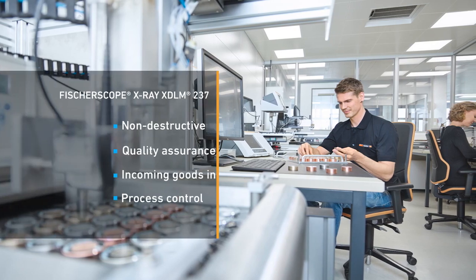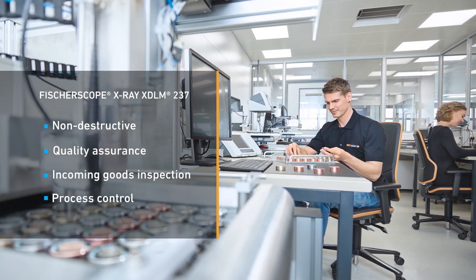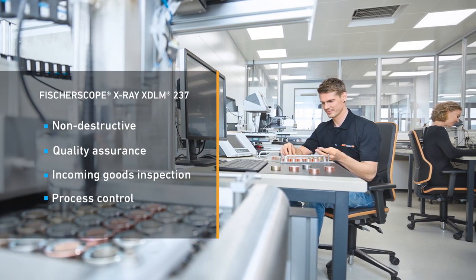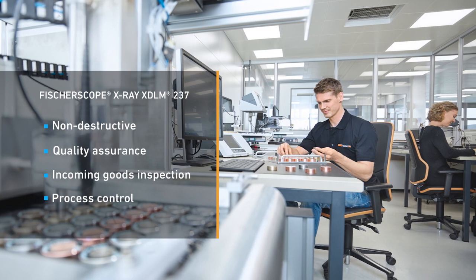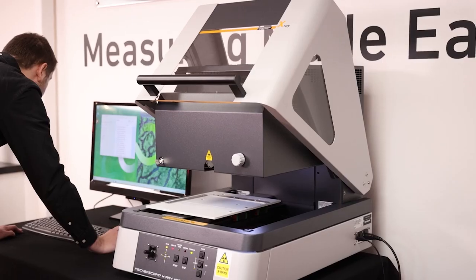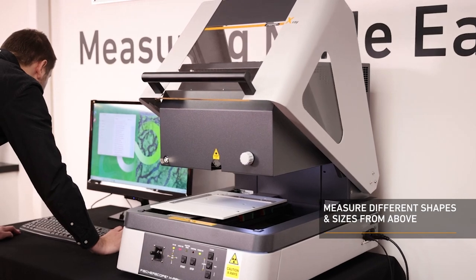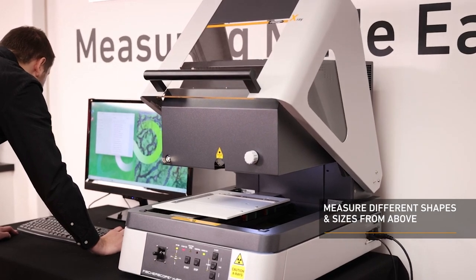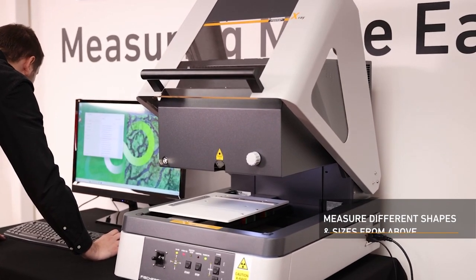With its fast, programmable XY stage, it's the best solution for automated measurements with small or large samples, in quality assurance and production monitoring. The instrument has an X-Ray beam in a top-down measuring direction, so samples are measured from above.